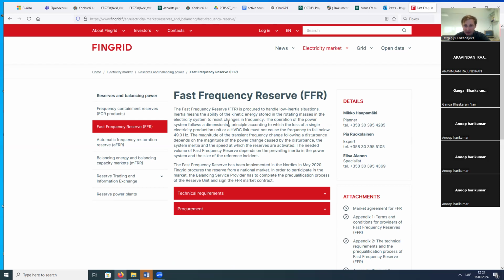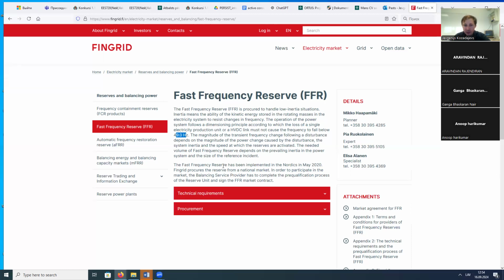The operation of the power system follows a dimensioning principle according to which the loss of a single electricity production unit or high voltage DC link must not cause the frequency to fall below 49 Hz. And this value is very important. The magnitude of the transient frequency change following a disturbance depends on the magnitude of the power change caused by the disturbance, the system inertia, and the speed at which the reserves are activated. The needed volume of the fast frequency reserve depends on the prevailing inertia in the power system and the size of the reference incident. The fast frequency reserve has been implemented in the Nordics in May 2020.